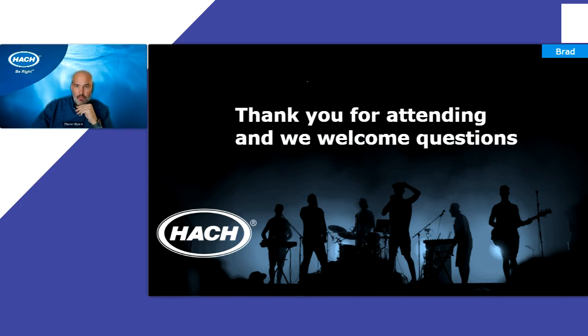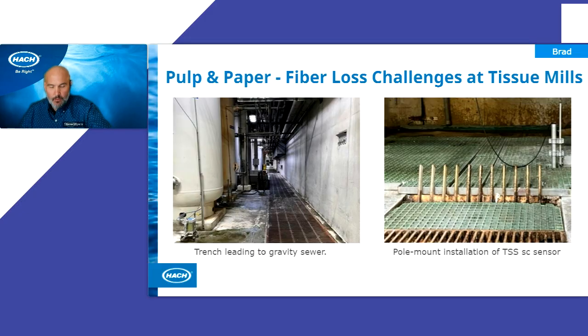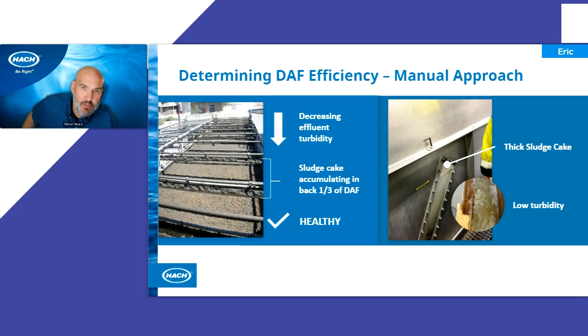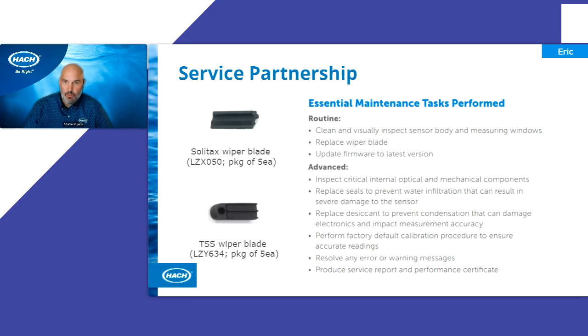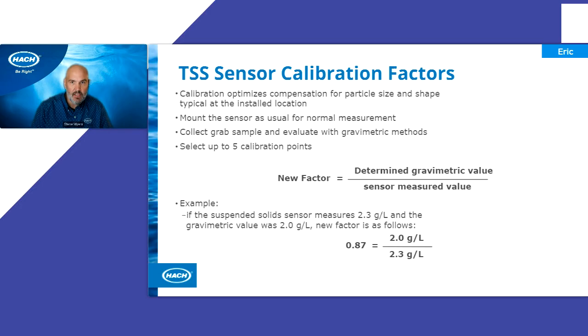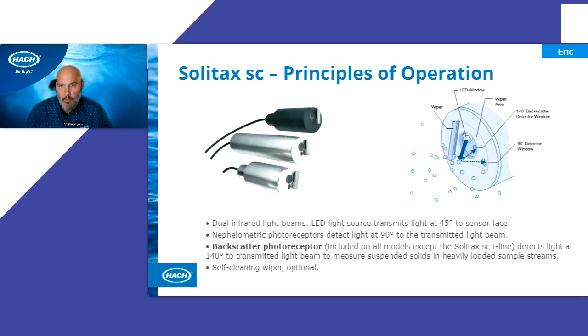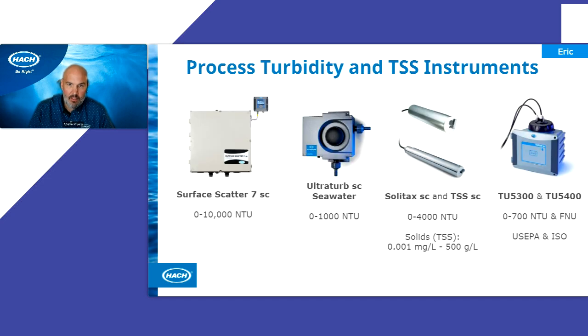So this is a question I'm going to answer from a functional standpoint, just from what I've observed in the real world. I've been at activated sludge treatment systems where they're using the Solitax or the TSS sensor for inlet water TSS for the activated sludge. That would be like 200 to 300 milligrams per liter for the inlet. Activated sludge tank, which would be 4,000 to 5,000 milligrams per liter.